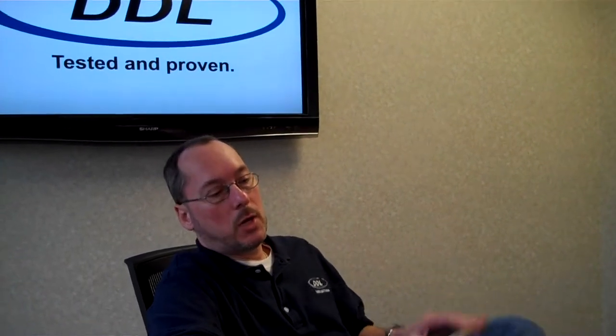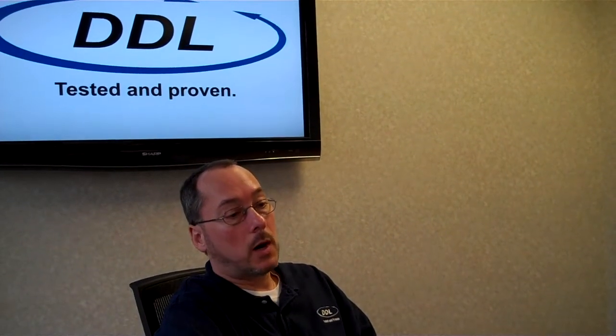To start off, could you please give us a quick overview of the standards for distribution simulation, ISTA 3A and ASTM D7386? Well, thanks, Claudia, for having me. There are a lot of different test methodologies that medical device manufacturers can utilize on a daily basis to validate their shipping or performance testing of their goods. Two of the most robust test procedures in the industry right now are ISTA Project 3A as well as ASTM D7386. They both address what basically transpires in a normal distribution environment: drop testing, vibration testing, compression testing. Both test methodologies are pretty close, or I'll almost call them identical to one another. It's just a different flavor, potato and potato.